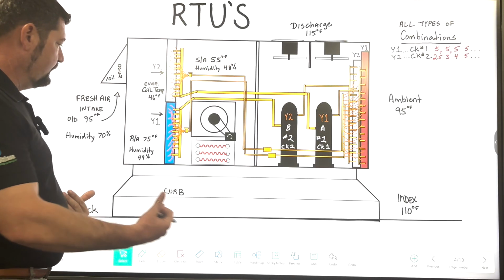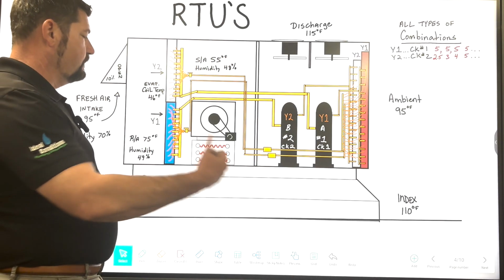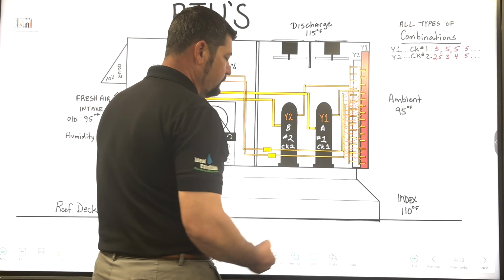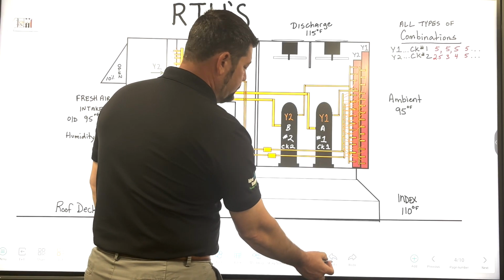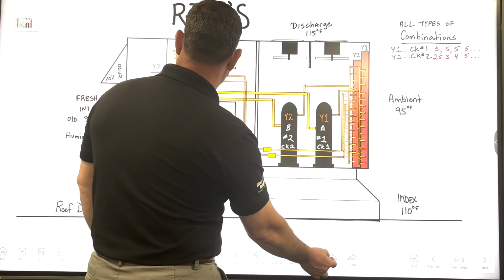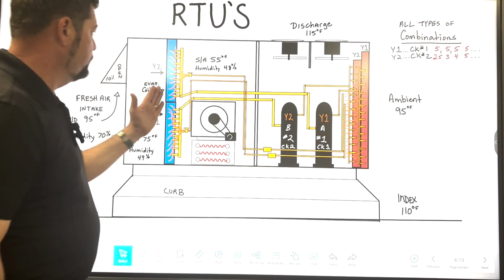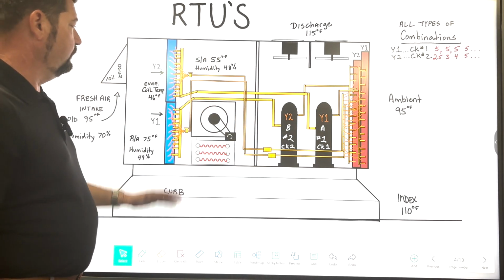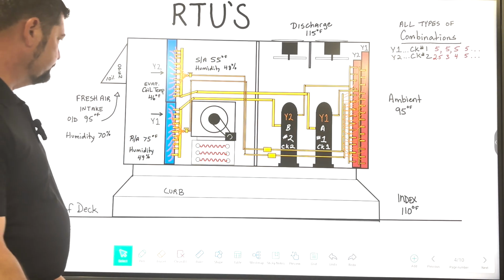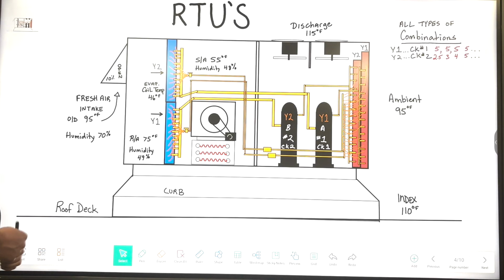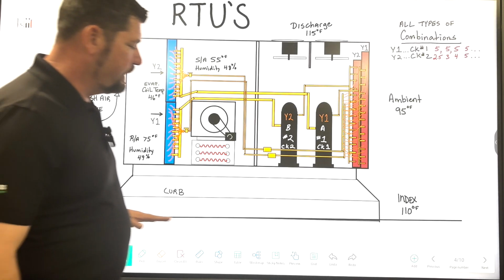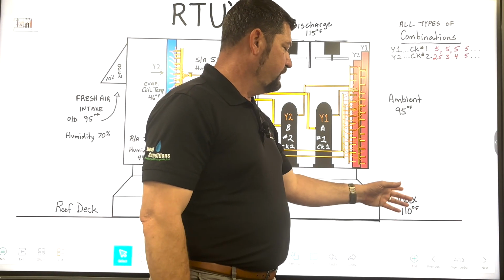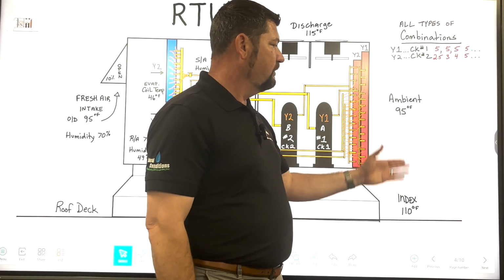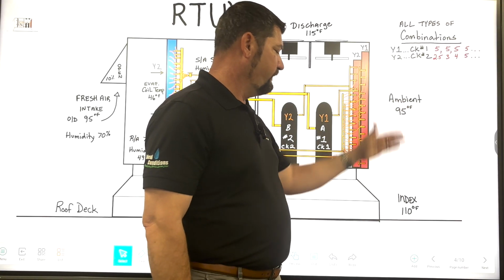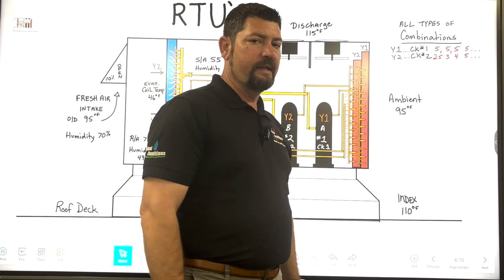And then when you need a higher BTU, we'll go ahead and just stage it back up so it'll look like this where we're running 2 circuits. Okay, going over the anatomy a little bit more, we got the roof deck down here. I put down here a heat index of 110 because if the outdoor ambient temperature is 95 degrees, that roof deck's going to be a lot warmer.